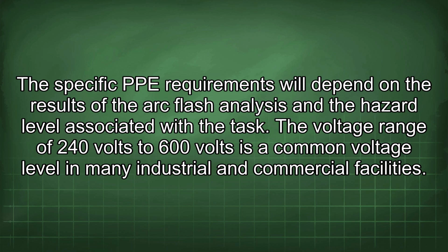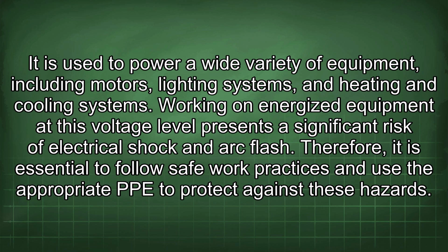The voltage range of 240 volts to 600 volts is a common voltage level in many industrial and commercial facilities. It is used to power a wide variety of equipment, including motors, lighting systems, and heating and cooling systems. Working on energized equipment at this voltage level presents a significant risk of electrical shock and arc flash. Therefore, it is essential to follow safe work practices and use the appropriate PPE to protect against these hazards.